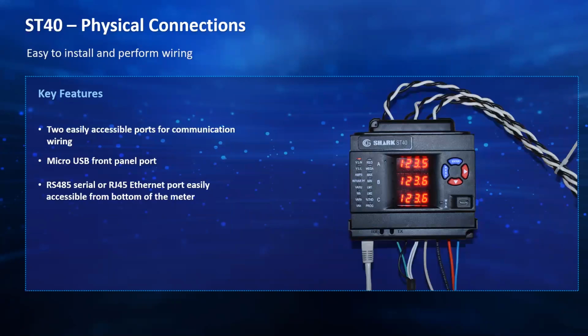Here we have a picture of the unit itself. The top of the meter, you can see the current inputs for our 3 current transformers. The bottom of the meter, we have our 3 voltage inputs, neutral input, as well as a power supply input. This meter does have a separate power supply from the A, B, and C voltage inputs.